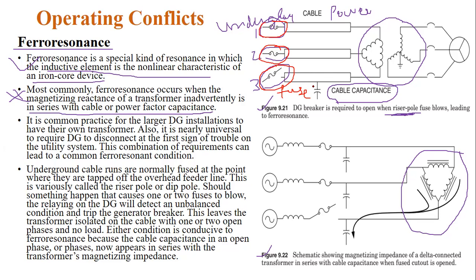This is separated from the system because of some additional part in this system. So this fuse is open. What will happen here? Only this transformer is connected to two lines. That means one and two cables only. The third cable is open. So this is the case.